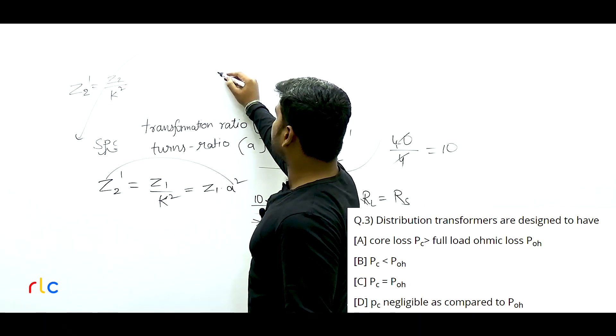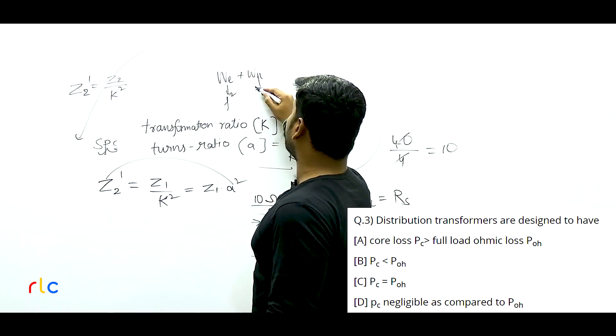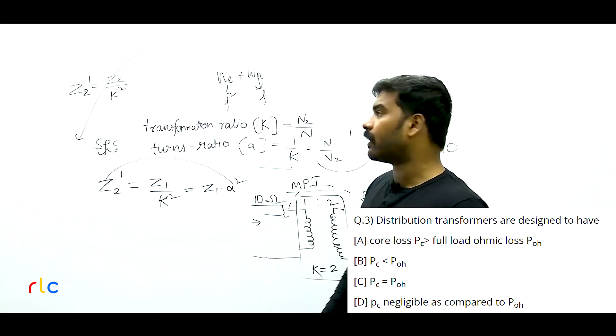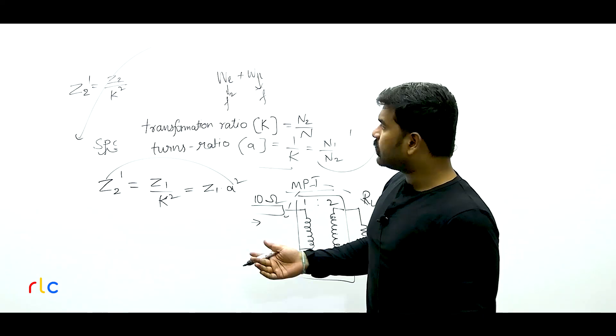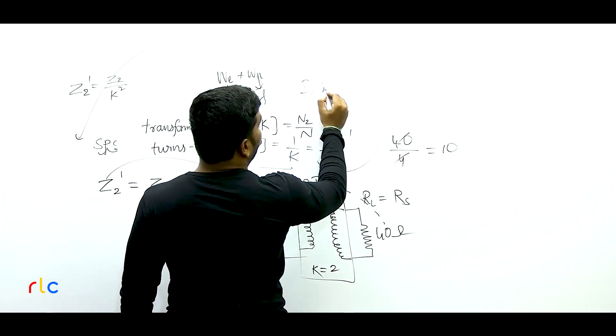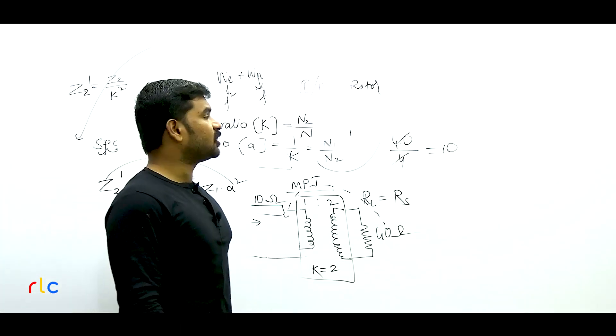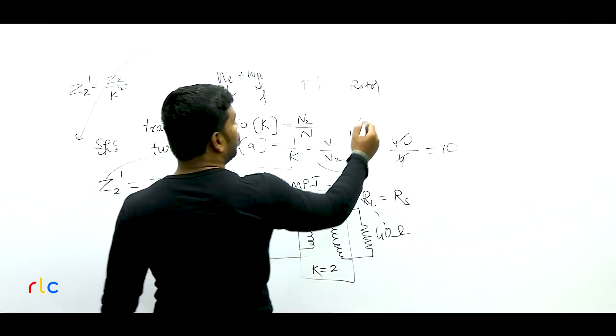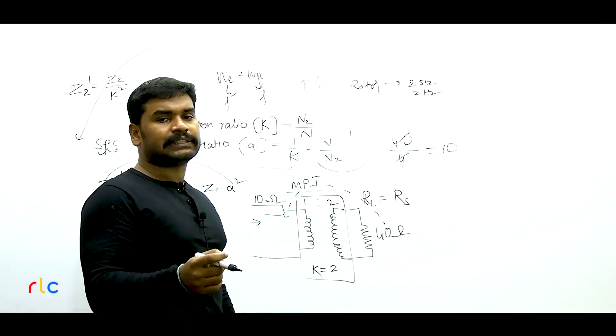If IC creates core losses (heating), it must be in-phase with voltage — just like resistive current. A resistor is the only component that creates heating losses. So IC must be in phase with the supply voltage. If voltage is at 0 degrees, IC is also at 0 degrees. For IM, it is the magnetizing current used to create magnetic flux — inductors create magnetic flux. The current in an inductor lags by 90 degrees, so IM lags voltage by 90 degrees.